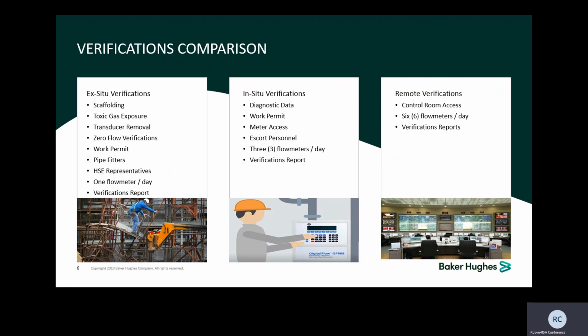From there, they're able to determine a pass or no pass. If there's a red flag, we're obviously not going to hand out verification reports if they're not passing - if there's a no pass, we'll perform an ex-situ. We did a study and we're about 87 to 90% passing on in-situ verifications. The benefit is because we're not doing scaffolding or removing transducers, we get to about 3 meters per day, so instead of spending 15 days on site, we're spending about 5 days.